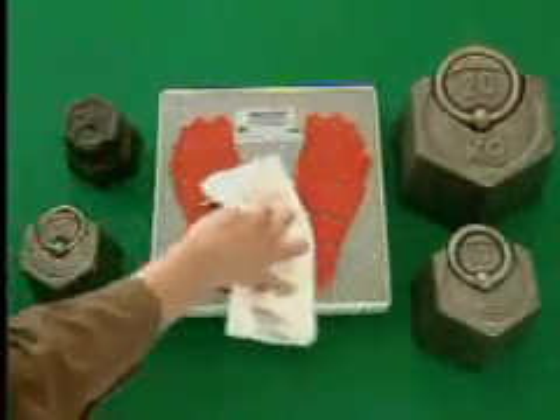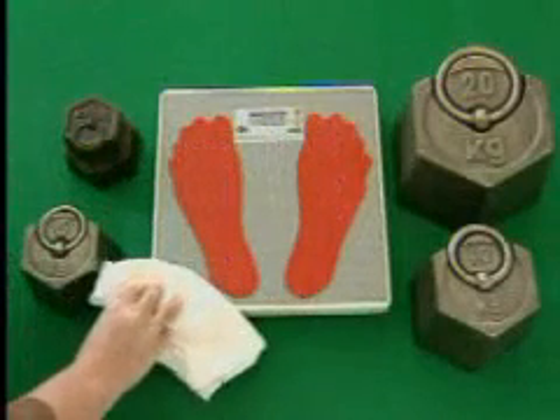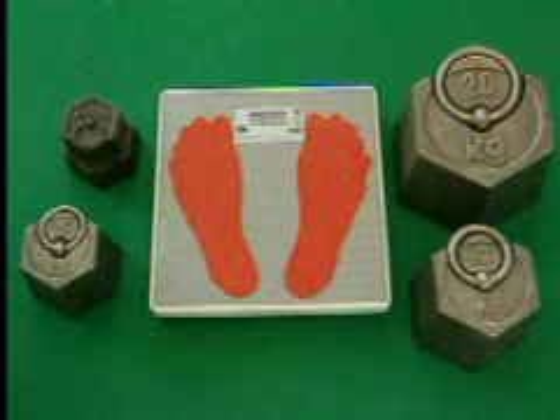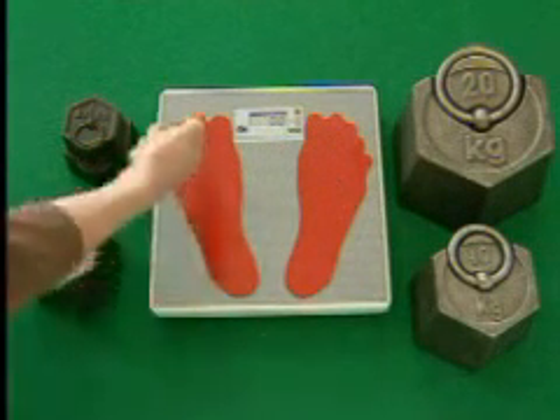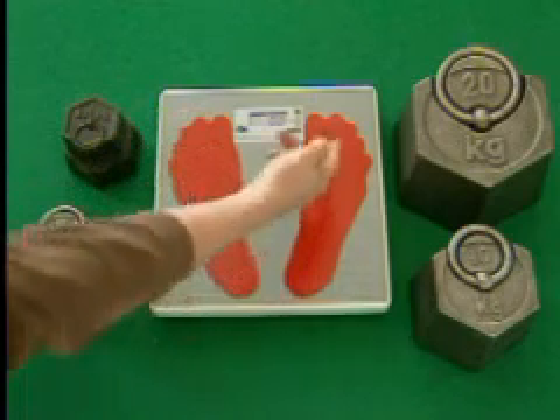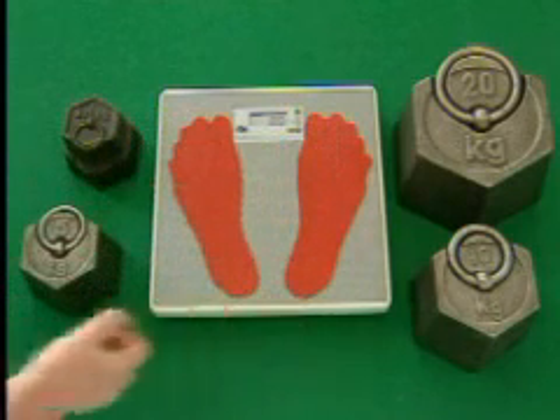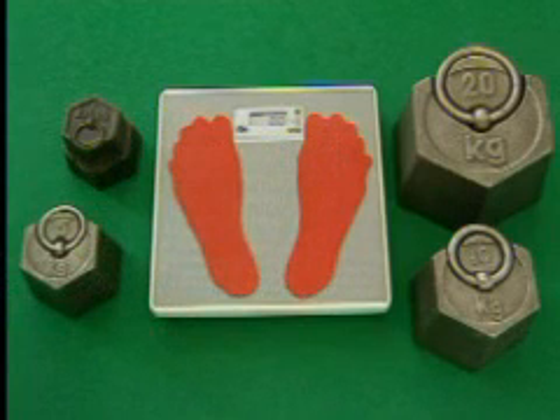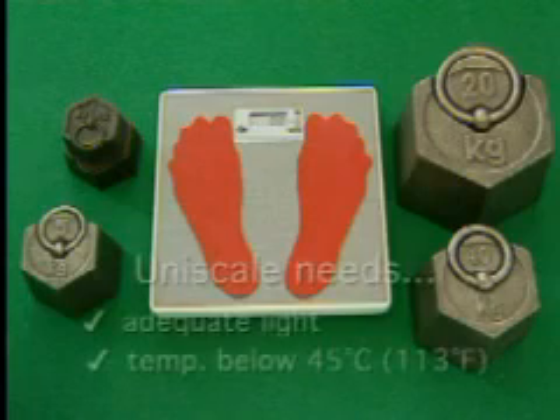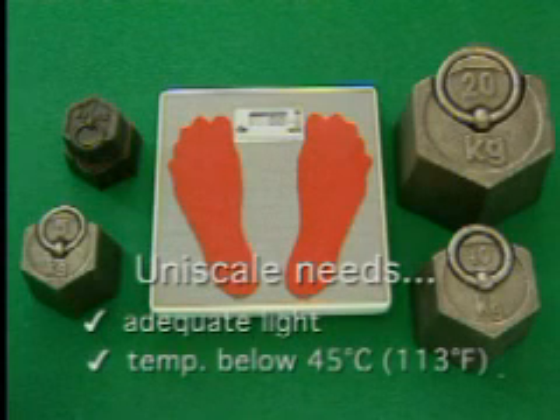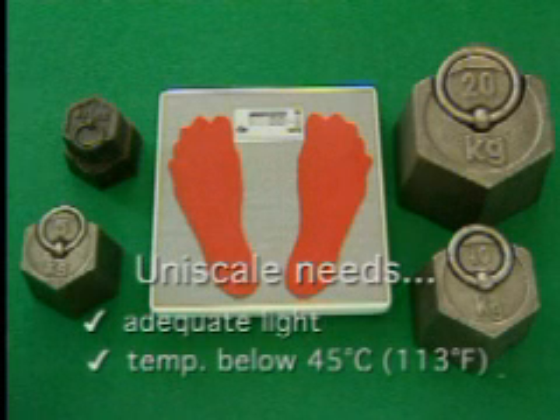The surface of the scale should be clean. It is recommended that foot marks be pasted on the scale to indicate where subjects should stand. This will ensure that the subject's weight is evenly distributed on the scale. The temperature in the room where the scale is used should not exceed 45 degrees centigrade. The uniscale does not function properly at higher temperatures.